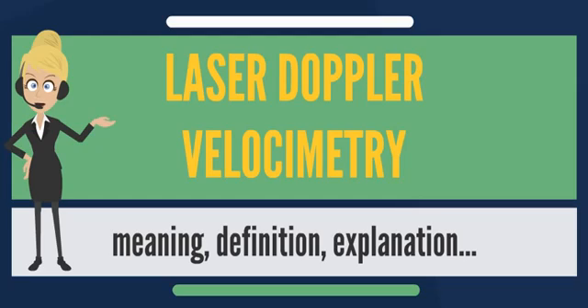Another form of LDV, particularly used in early device developments, has a completely different approach akin to an interferometer. The sensor also splits the laser beam into two parts: one, the measurement beam, is focused into the flow, and the second, the reference beam, passes outside the flow. A receiving optics provides a path that intersects the measurement beam, forming a small volume.